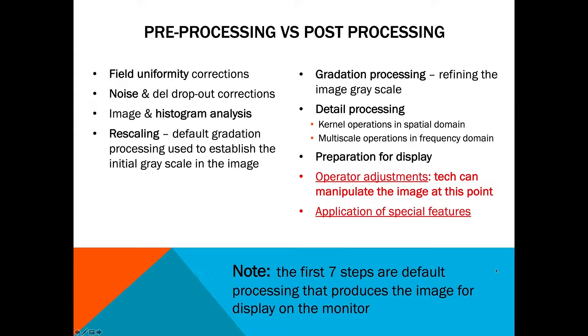Here's a great summary slide on pre-processing versus post-processing. The first seven steps — field uniformity, noise, histogram analysis, rescaling, gradation processing, detail processing, and preparing for display — are all pre-processing functions handled by the software. It's not until you get to the operator adjustments that the tech or radiologist can manipulate the image, where special features like edge enhancement and smoothing can be applied. These first seven steps are called default processing, which produces the image for display on the monitor.